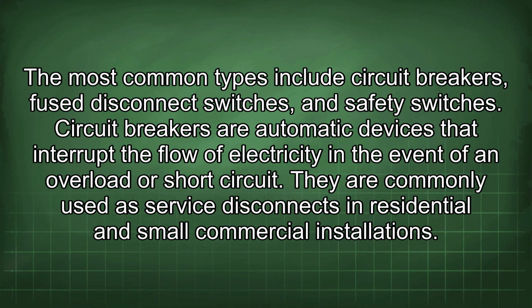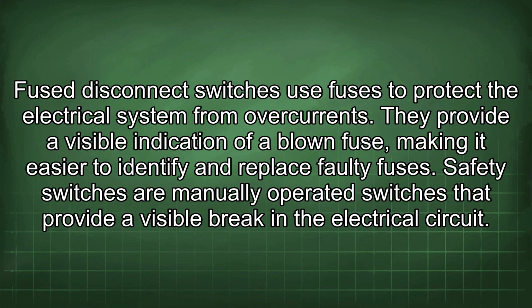The most common types include circuit breakers, fused disconnect switches, and safety switches. Circuit breakers are automatic devices that interrupt the flow of electricity in the event of an overload or short circuit. They are commonly used as service disconnects in residential and small commercial installations. Fuse disconnect switches use fuses to protect the electrical system from overcurrents. They provide a visible indication of a blown fuse, making it easier to identify and replace faulty fuses.